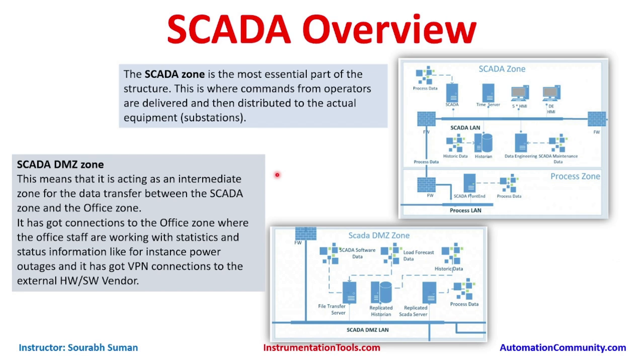The SCADA zone is the most essential part of the structure. This is where commands from operators are delivered and distributed to the actual substations. In the SCADA zone we see SCADA taking all the process data, HMIs, a time server for synchronization, a historian similar to DCS, maintenance data, and communication to the process zones.